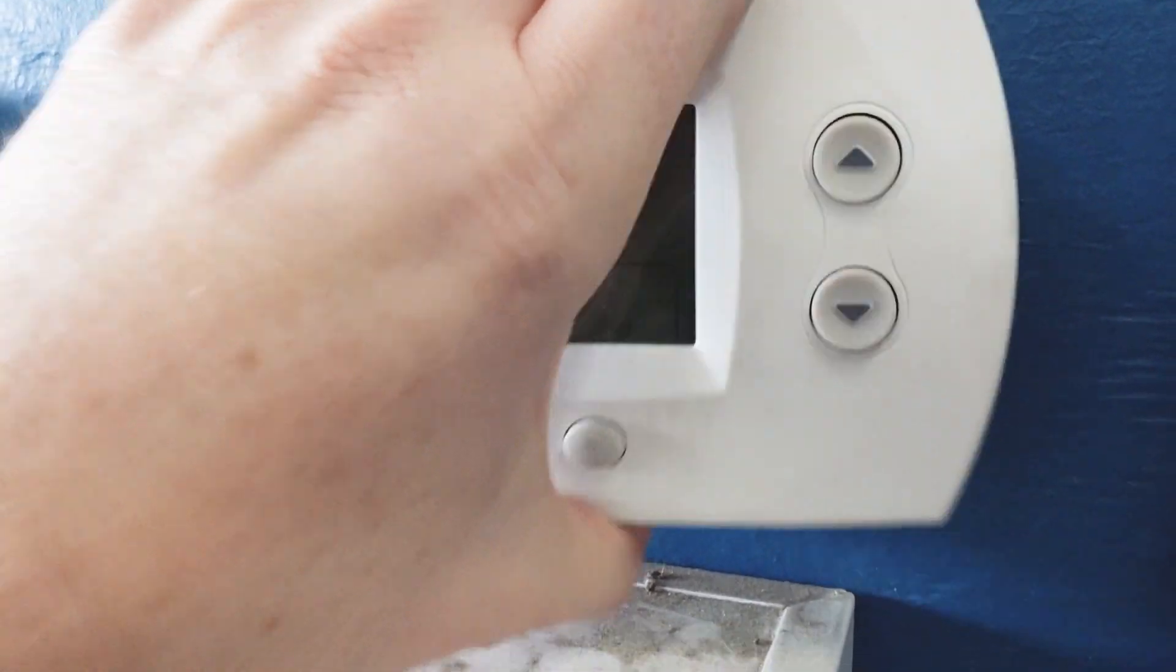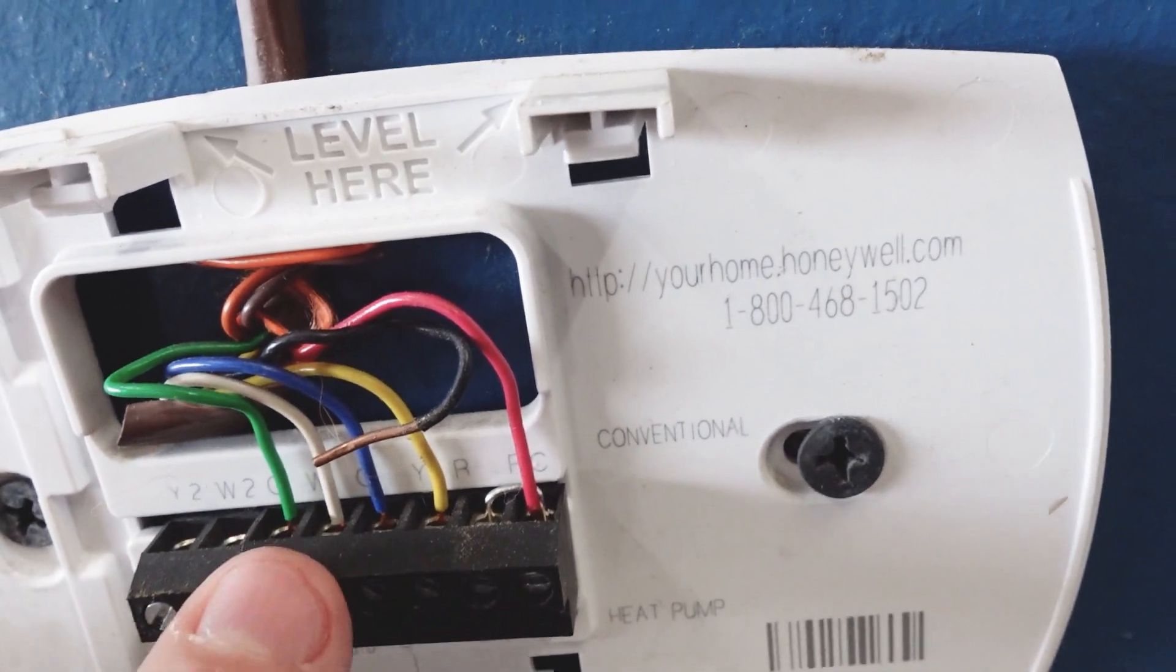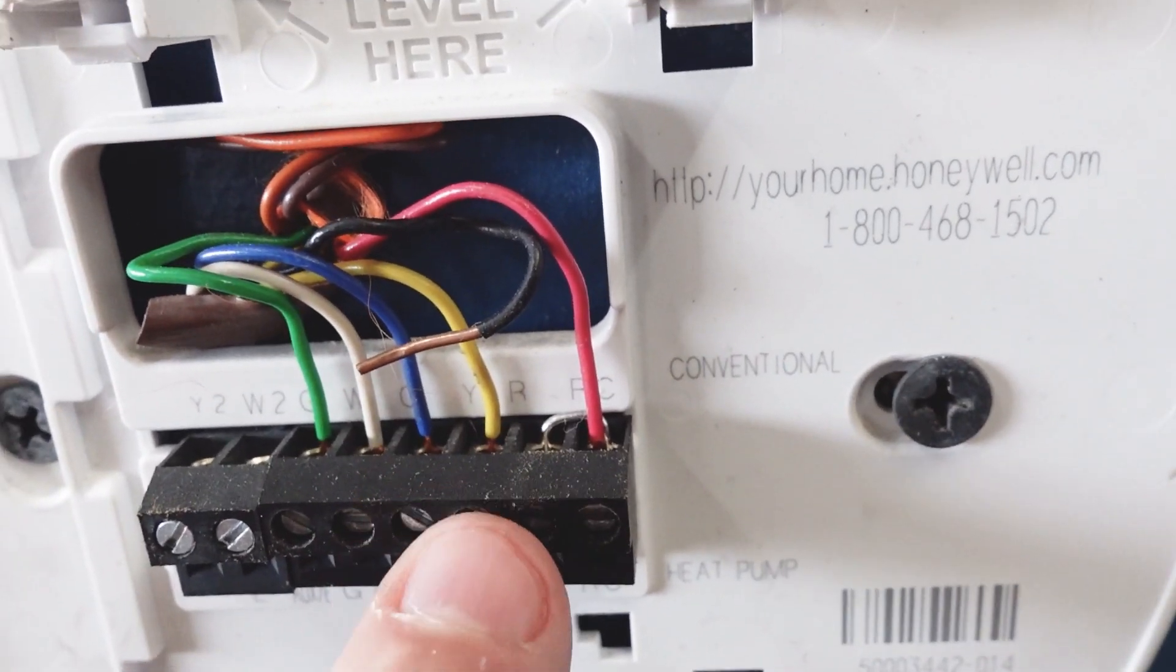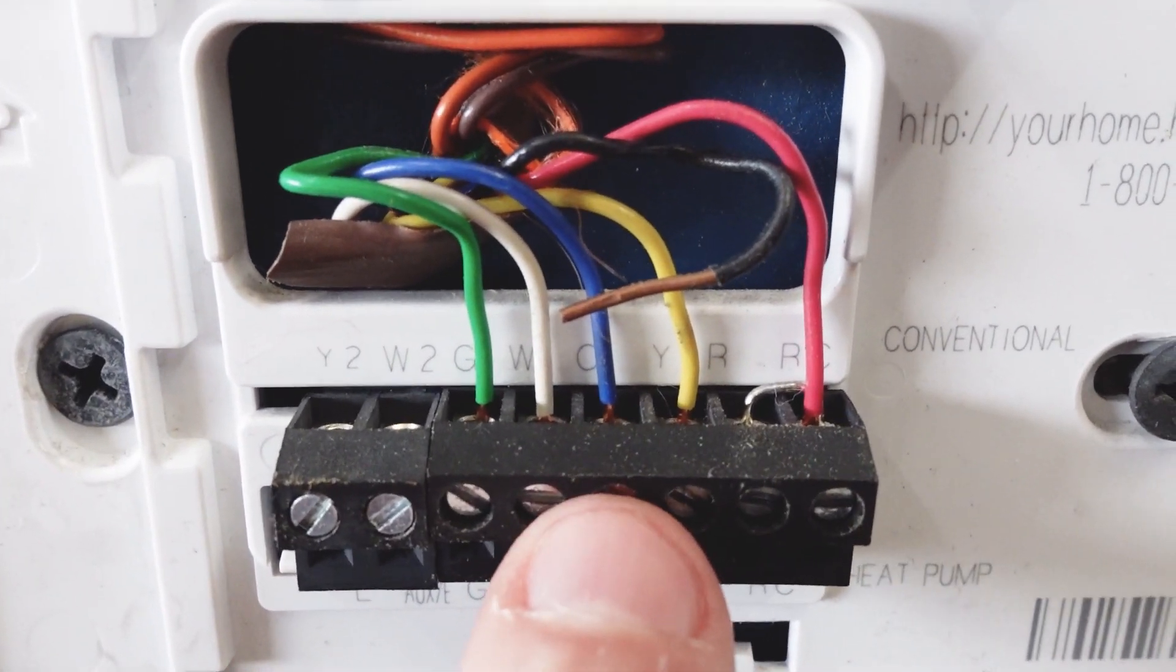Inspect your thermostat. All the connections should be neat and tidy and connected to the proper terminal. If you have bare wires, that could be the cause of your problem. Also ensure that your common is connected to the C terminal.